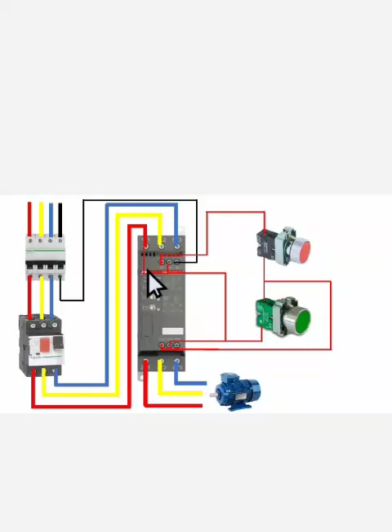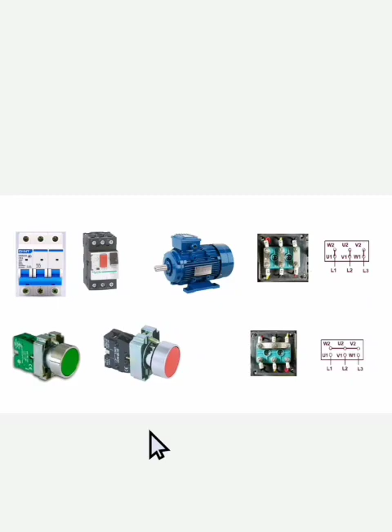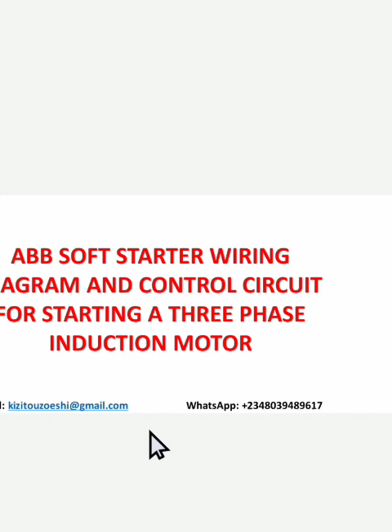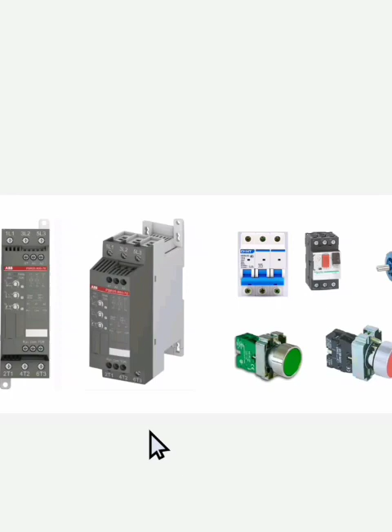Instead of using direct online or star delta starting, we have a more interesting approach for starting an induction motor. We can start with star delta, but sometimes the inrush current may be too much for it to handle. That's why we employ an ABB soft starter.